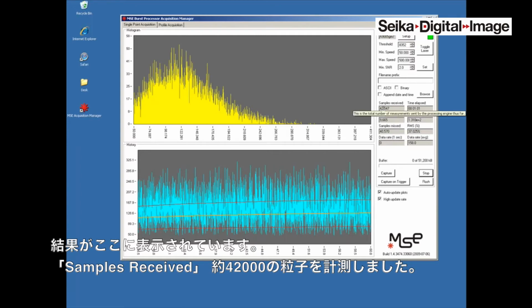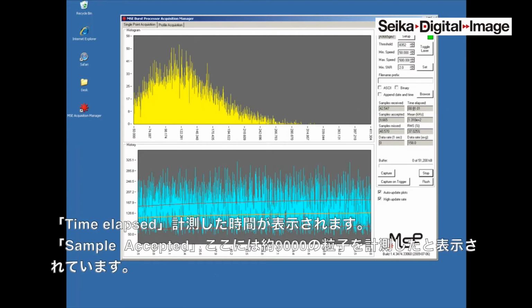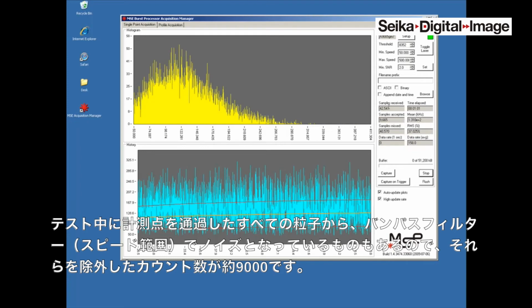We've captured 42,000 samples here in about 1 minute and 1 second. Of these, we've accepted 9,000 samples. The way we accept is that each sample goes through a number of tests, including the test of signal to noise and the test of the bandpass filter. If it satisfies all conditions, it's accepted and used in the calculation of the mean. Otherwise, it's discarded. So in this case, we have a lot of samples that were discarded for some reason.